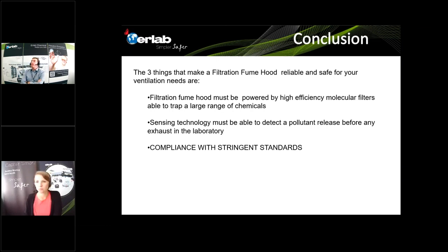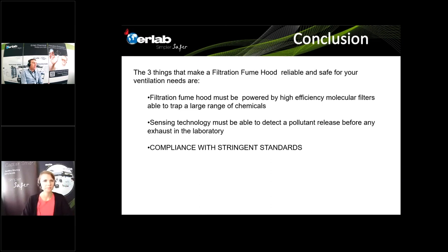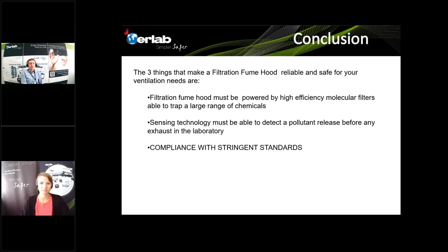How often does the unit need sensor calibration for pollutant detection? We calibrate the sensors before installing them in the unit. What we recommend afterward is not recalibration on site — which is expensive — but replacement. We monitor sensor variation over time. For VOC sensors, we recommend replacing them every five years. For acid sensors and formaldehyde sensors, we recommend replacement every two years. There is no on-site calibration.